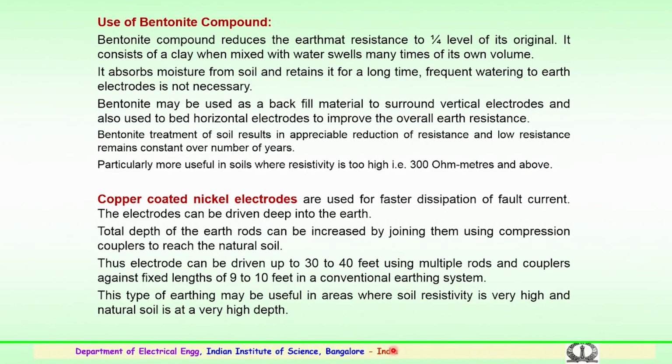This type of earthing system may be very useful in areas where soil resistivity is very high and the natural soil is at a very high depth. In such cases, going in for copper coated nickel electrodes will be very useful to reduce the earth resistance in the area.